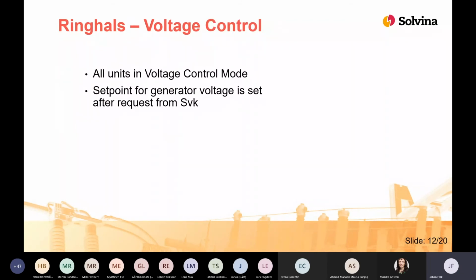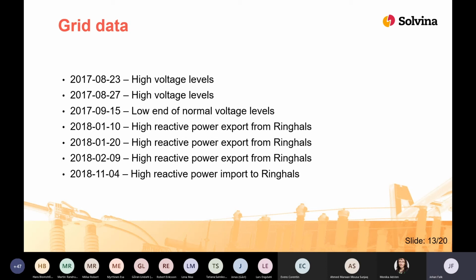And regarding voltage control at Ringhals, the AVRs of all the generators at Ringhals are always in what we call voltage control mode. This means that each generator has a voltage set point value that the AVR tries to maintain. And the reactive power will then change according to the grid voltage. The set point for the voltage only changes after a request for change has been received from Svenska Kraftnät. And after a change in the set point, the new value remains until a new request is received, or until the unit, of course, is disconnected, and during synchronization it will receive a new value. And this value will be kept until they hear something from Svenska Kraftnät. So now we will start looking a bit more at the historical data that we have analyzed and visualized.